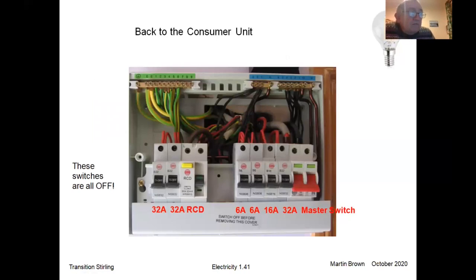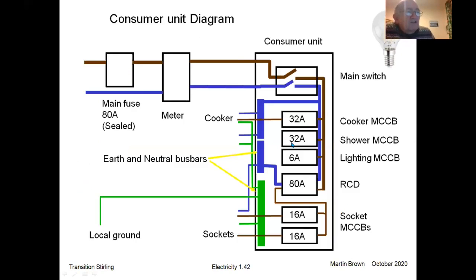Okay, so that's our consumer unit. If we draw up the consumer unit, and this time I've used the right colours, basically, that's what the circuit looks like. And I won't go into the detail, but you get the idea. Here's the power going out to the sockets, protected by the MCCBs and also by the residual current detector. Here's the power going to the cooker. That's not protected because it's much higher power. And here's some other connections that are there.